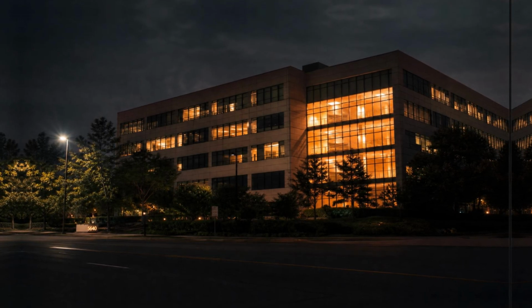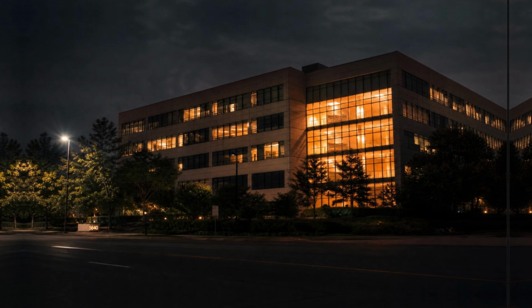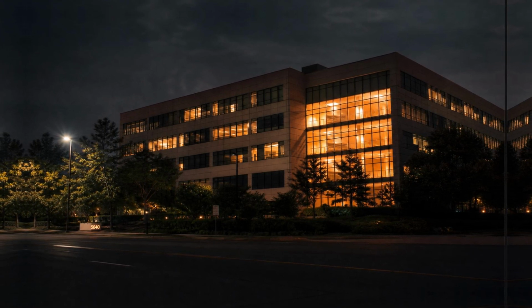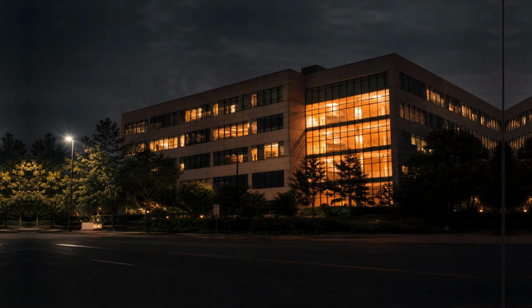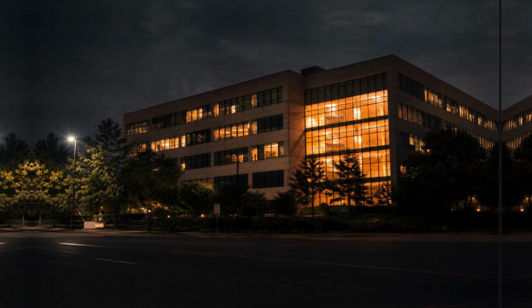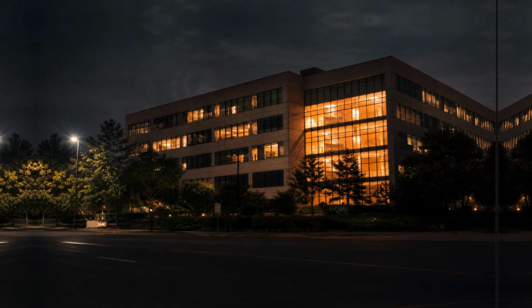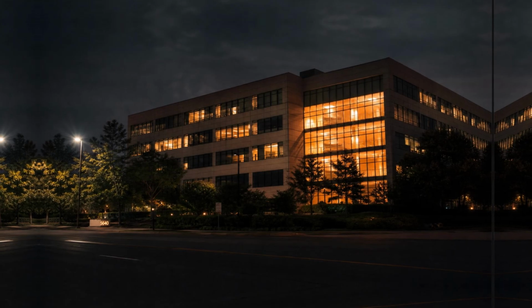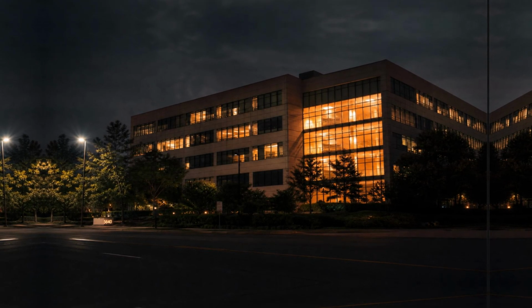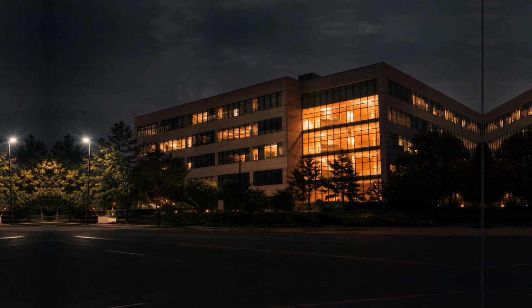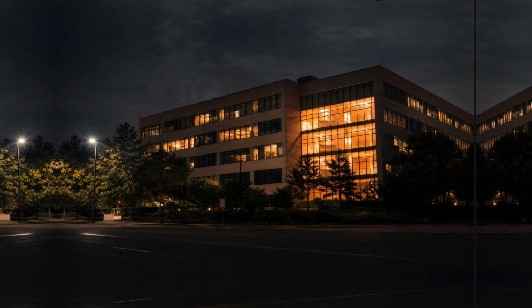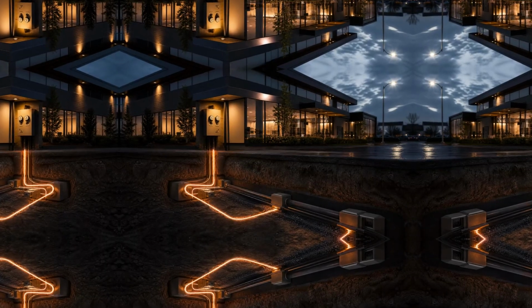And somewhere nearby, in a cabinet that may not even carry any obvious label from the outside, a monitoring system is watching. It is watching the incoming utility power with great care and great patience and no particular drama. Utility power monitoring is, in its essence, the practice of observing the characteristics of the electricity arriving from the power company, and continuously checking whether those characteristics fall within acceptable limits. It is quiet work, continuous work, the kind of work that happens in the background every second of every hour, and that produces no visible activity at all when everything is as it should be.